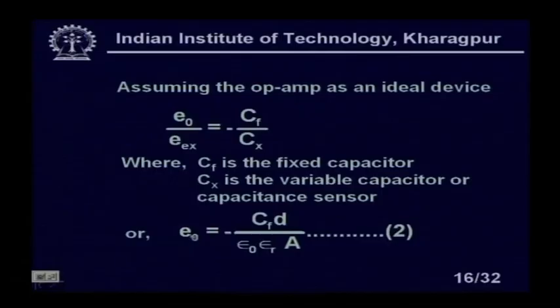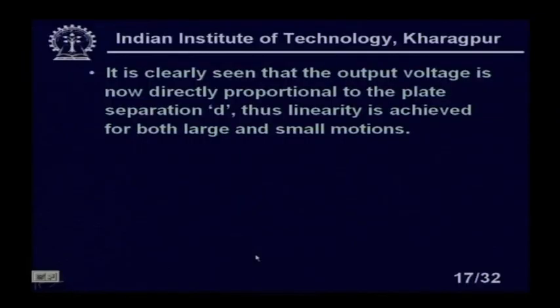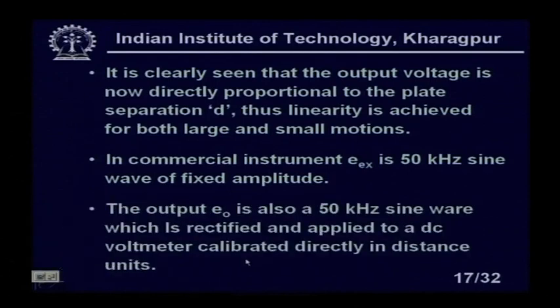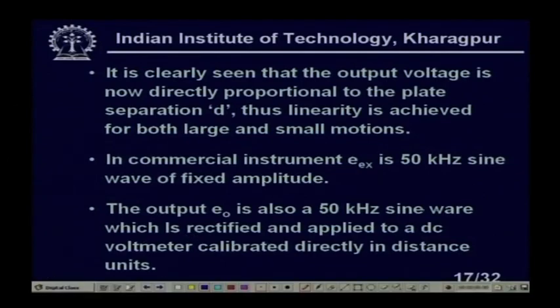The output voltage is now directly proportional to the plate separation D, so linearity is achieved for both large and small motions. In commercial instruments, the excitation Eₓ is a 50 kHz sine wave of fixed amplitude, and the output E₀ is also a 50 kHz sine wave.